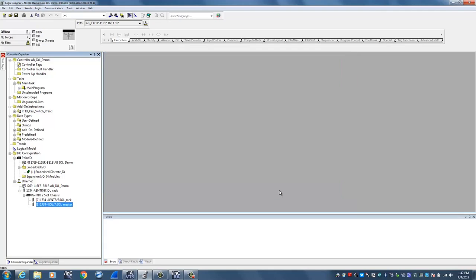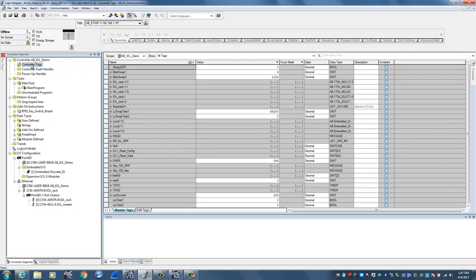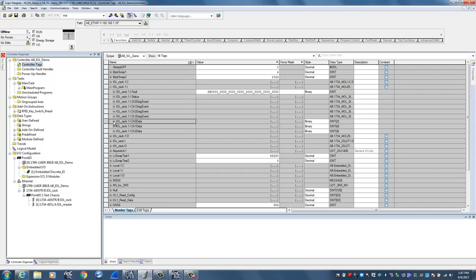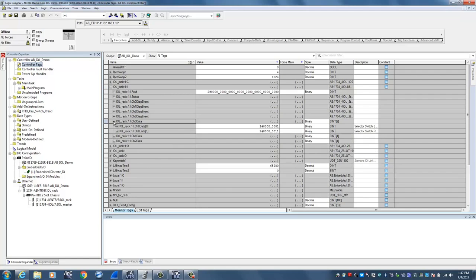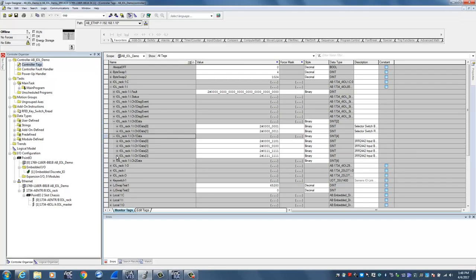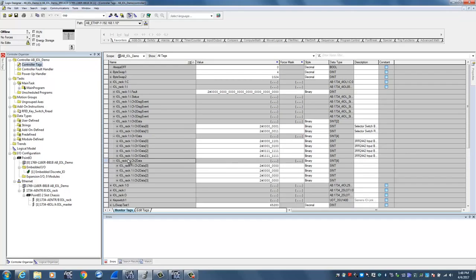When you do that, at the same time some controller tags are also generated. So if I open up controller tags here, you'll see under the IO-Link rack configuration under inputs, you'll see some data tags here for channel 0, channel 1, and channel 2. If I expand the information for channel 0, you'll see from the RFID key switch it's going to provide two bytes of input data coming into the Rockwell system using those data tags. And then for the current monitoring relays under channel 1 and channel 2, you'll see those monitoring relays supply four bytes of cyclic data per device.